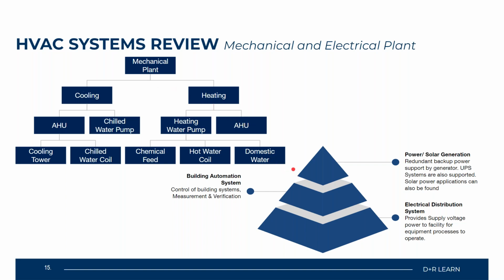Now, over on our electrical side of the house, we have a few different things happening within our electrical plant. Power and solar generation is one of them: the use of generators to supplement secondary or redundant power from any power loss that may have occurred from your commercial or primary power source. You'll also have all of the setup for your solar applications located at your electrical plant. Electrical distribution systems are also part of your electrical side, where your transfer switches, motor control centers, transformers, and also your UPS systems are located. And lastly, your BAS, or building automation system, which is used for measurement and verification, and also the control of building lighting and mechanical and electrical services.